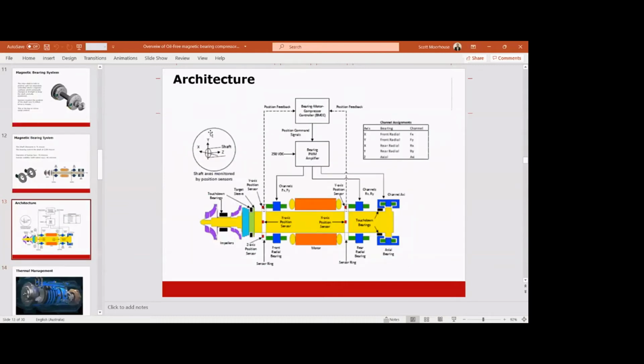I won't go too far into the architecture of how the bearings work, but we take the sensor inputs and we go into what we call our bearing motor controller. That bearing motor controller gives an output to a PWM, or a pulse width modulator, telling the bearings how much 250 DC needs to go to the bearings to position the bearings. And we have multiple X, Y, and Z position sensors that we look at the shafts.